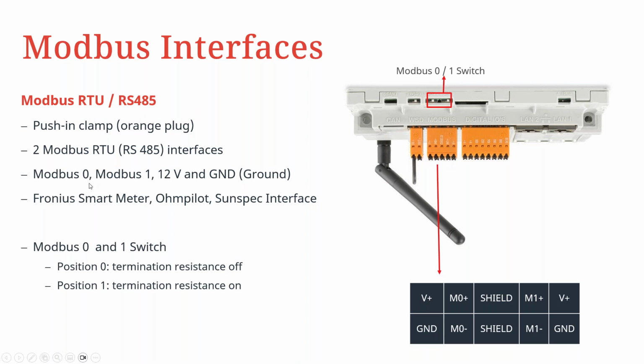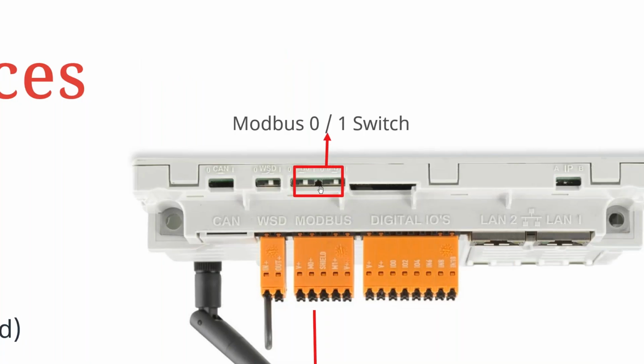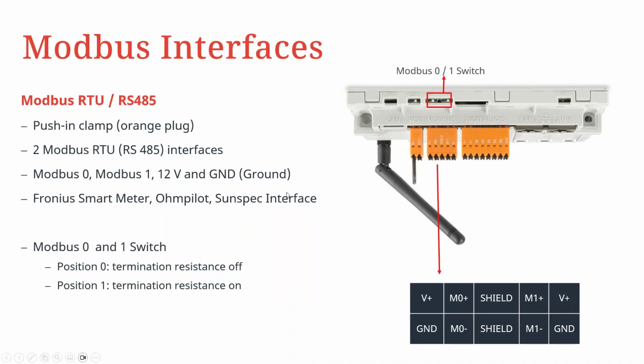We have their respective switches, as you can see in this case. Let me just zoom in a bit. So you can see the switches. So this is Modbus 0, and then this is Modbus 1. So ensure for communication purposes, the switches are supposed to be in position 1, that is switched towards the right-hand side. And then if properly implemented, they can be used for communication with the Fronius smart meter, Ohmpilot, and of course, for SunSpec interface purposes.